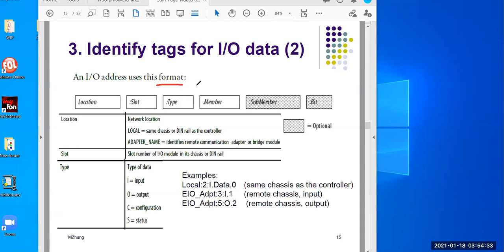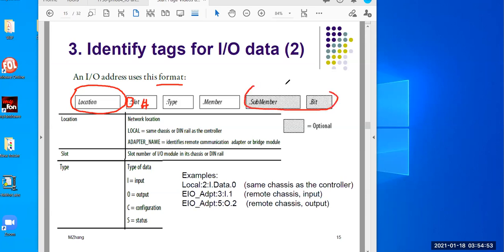Over here you can see the format — this is the structure or pattern I just talked about. This first part indicates the location, followed by a colon, then the slot number. After that comes type and member. Remember, the last two items — submember and bit — are from the Rockwell documentation and are optional; you don't necessarily need them all the time.